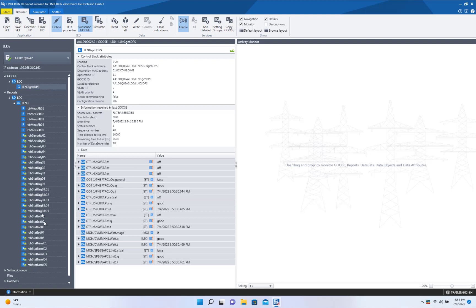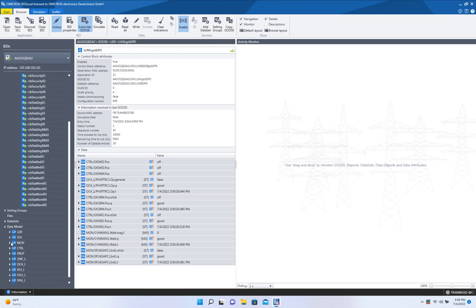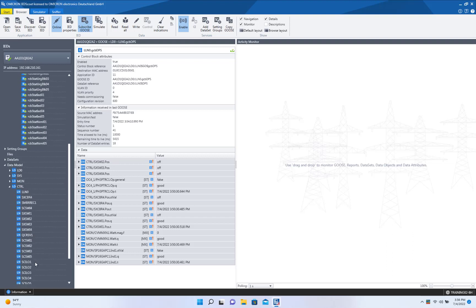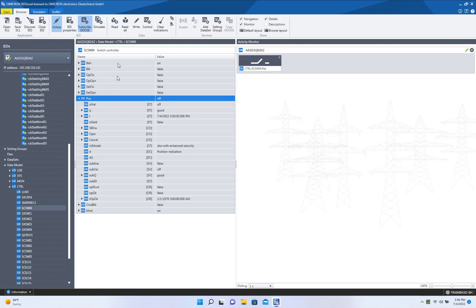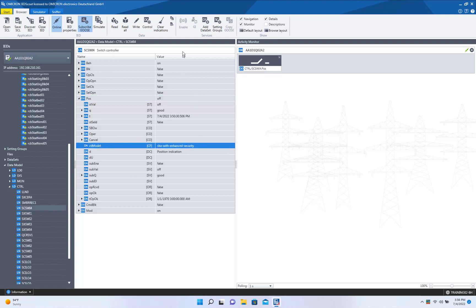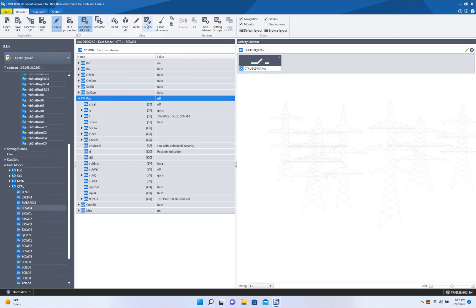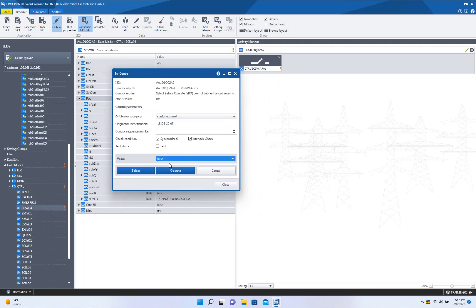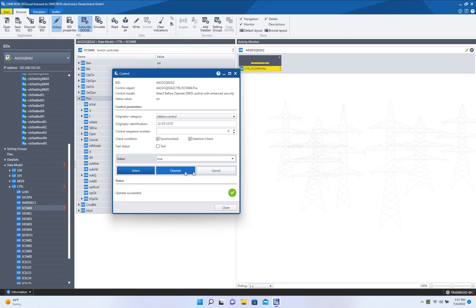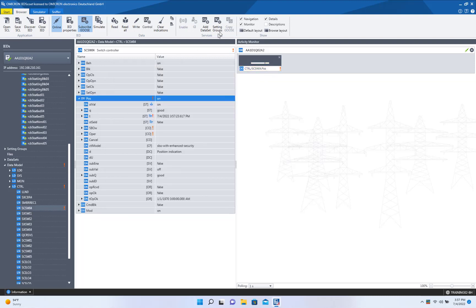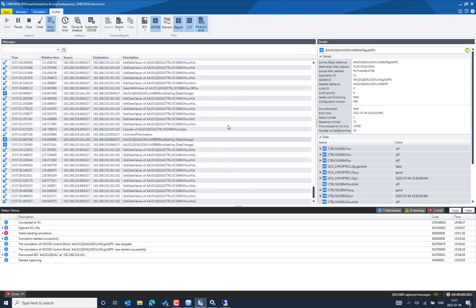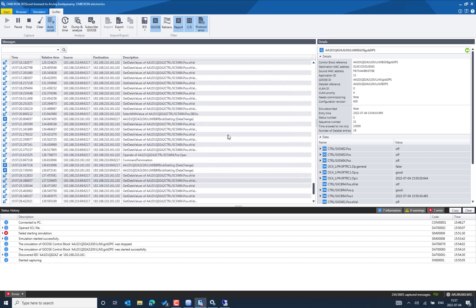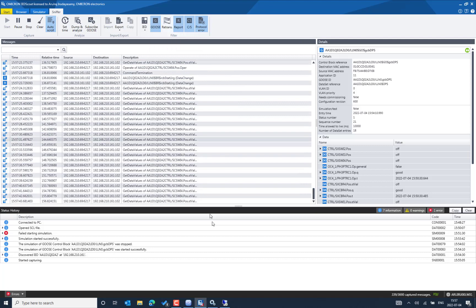You can also send control commands from the other client PC. Drag and drop to pick the right data object — this particular data object is a switch controller logical node. The control model is SBO-with-enhanced-security. Press the data object, check the control model, then change the position from true to false and operate. You can flexibly change the control command from the client application and it will be received by the IED. You can see exactly what is happening — the polling, client-server traffic — everything is easily understandable.